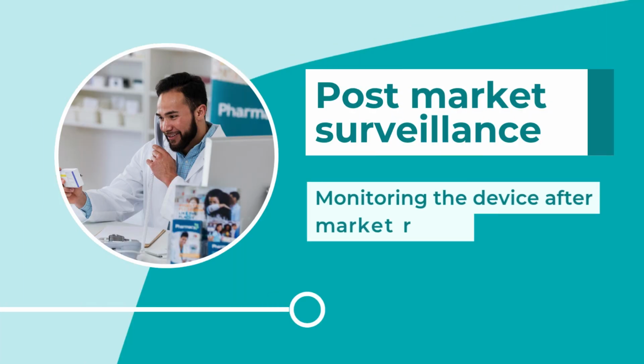After market entry, compliance continues. A post-market surveillance plan under Article 83 runs throughout the device's life. Class 2A, 2B, and 3 devices require periodic safety update reports, and any serious incident or field safety corrective action must be reported within the Article 87 timelines of 2, 10, or 15 days.